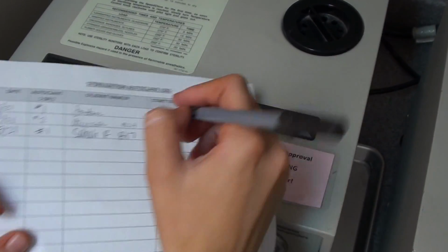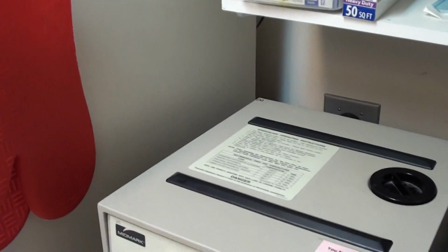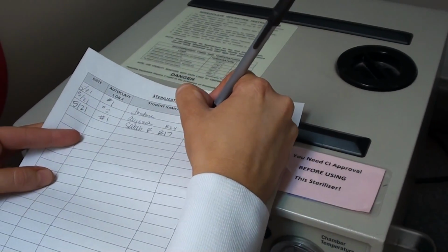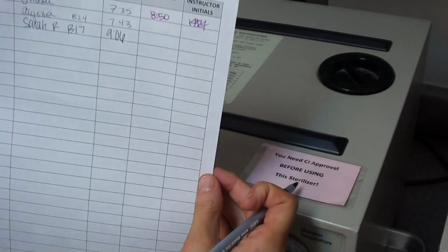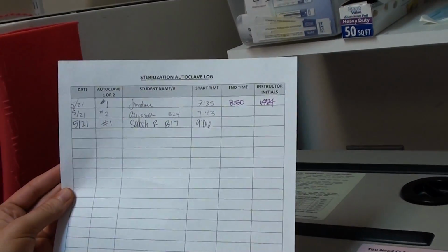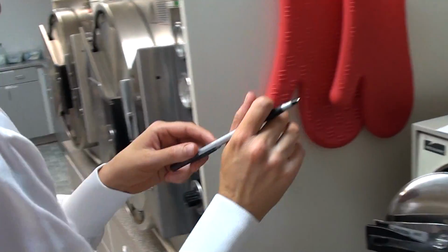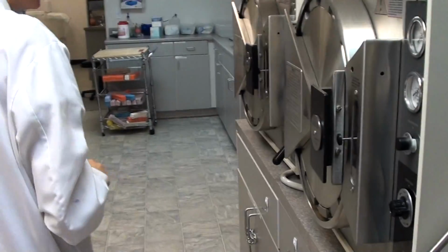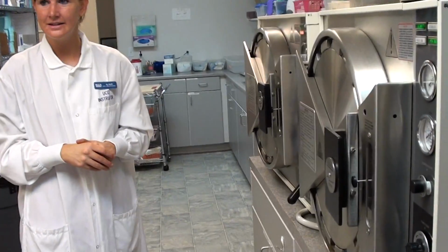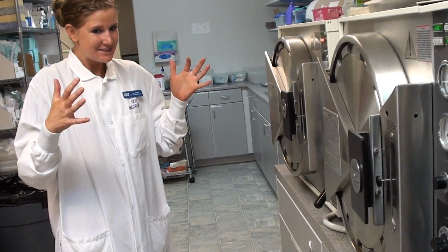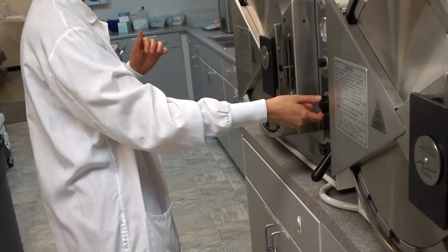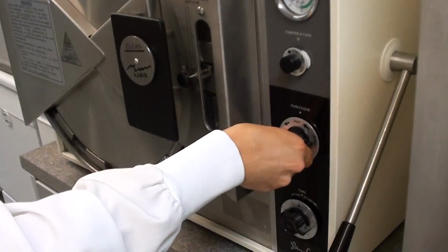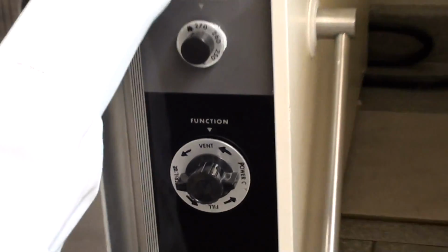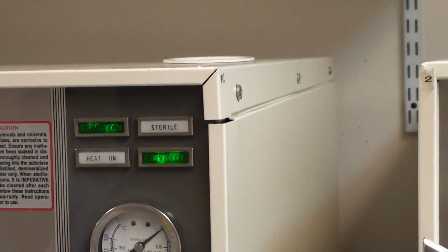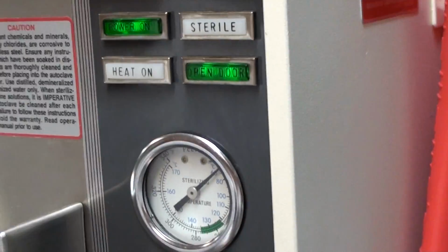And it is 9:06. Yes, it is. Now, after you hear the autoclave buzzing, through the magic of time, sterilization is over. She's going to turn the function control to vent and wait for the open door light to illuminate. Let's show them this one. Now we're magically switching to the one that already says to do that.